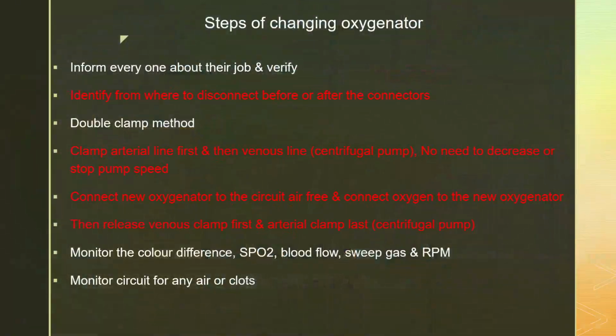Oxygenator change - again the steps remain the same. Only thing is you don't have to come down to zero flow, and you don't have to remove the pump, because you are changing the oxygenator, not the pump. So when you want to change the oxygenator, the steps remain the same. They'll show you how to do it.